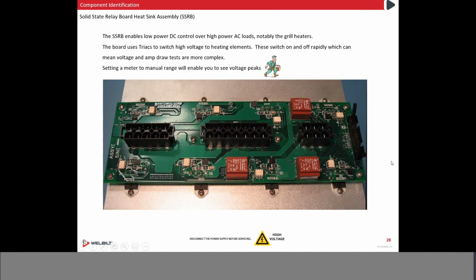All right, your solid state relay board is no different than what we've seen before. Remember, it basically allows the DC control over AC outputs to the heaters. Again, each triac has one LED light. Each triac's LED light will flash when it's delivering the appropriate power to the heating element. The reason why it's flashing is because it's pulsating power. So if I were to put an amp meter on my output to that, let's just say my front heating element, which is my front heating element here, it's going to pulsate on your meter because it's not a constant power that comes out. Okay, so you're not going to see a constant power. It pulsates. That's why it flashes.